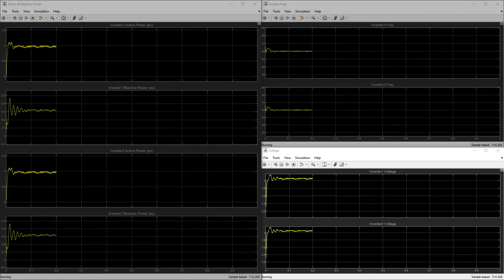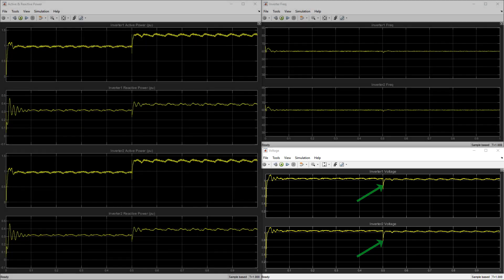This is the voltage scope of the connected inverters. We can see that both inverters' voltages are maintained around 1 per unit after the load switches on at around 0.5 seconds.